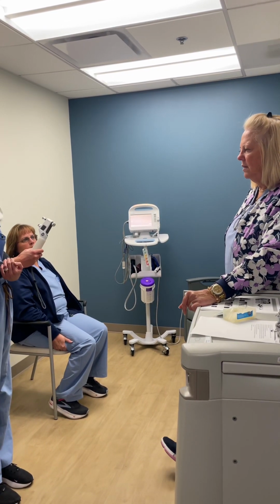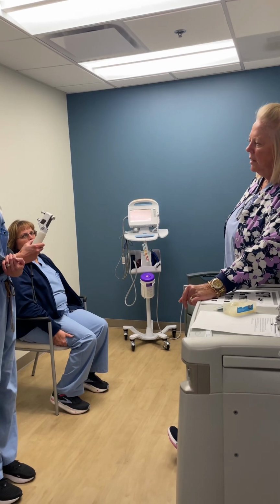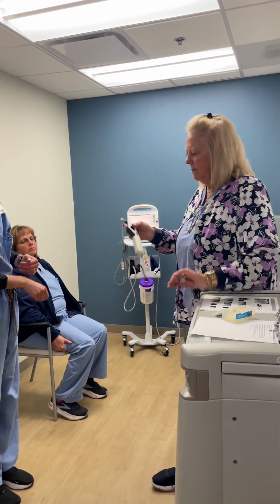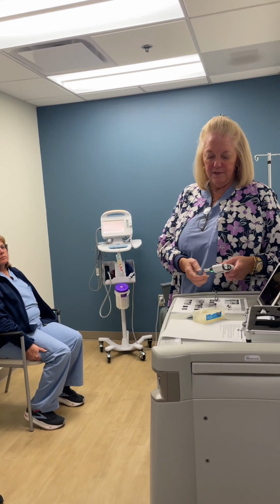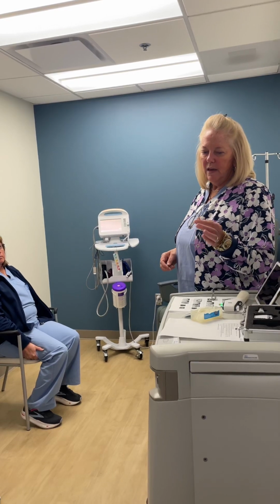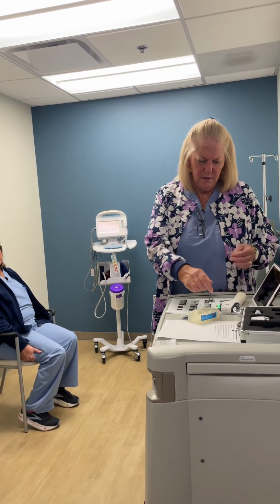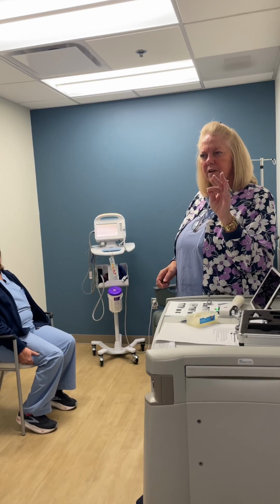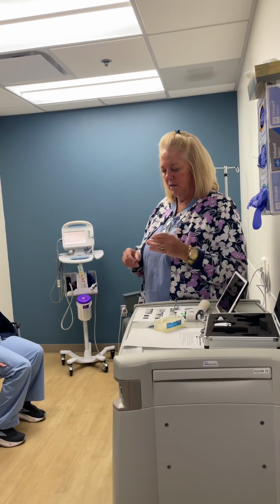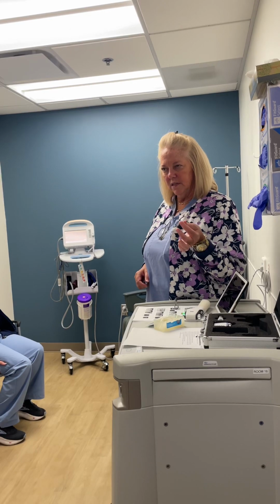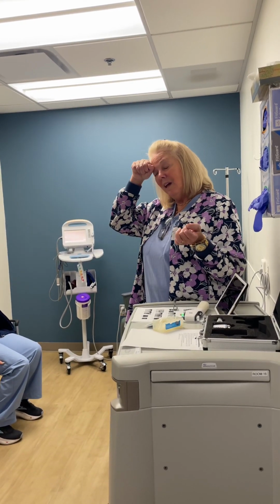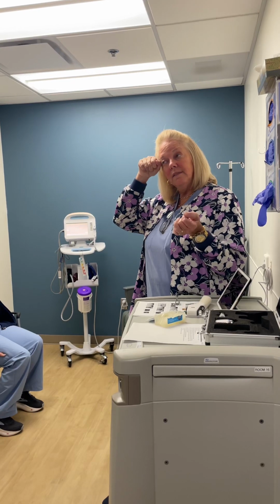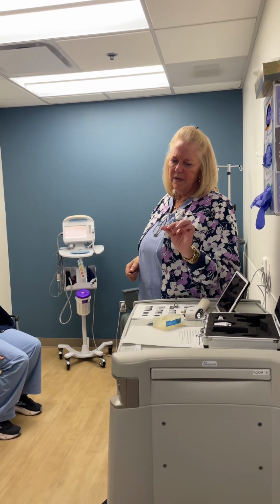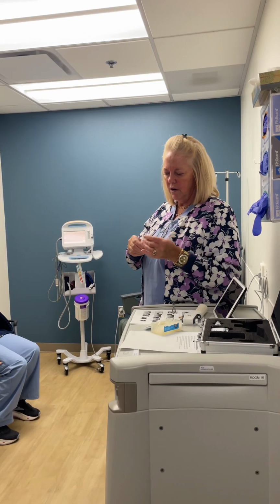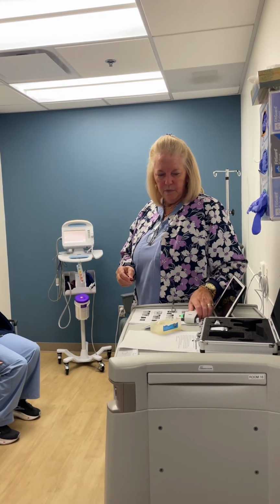What else can I say? Too high, too low. A lot of times with this model, you get static, and it's going to keep giving you an error message to repeat it. Take out the little piece here and rub it between your fingers, and that gets rid of the static. This piece also gets cleaned every 6 months. It gets soaked in alcohol. Actually, SPD will do it. They'll soak it in 70 to 100% alcohol and then rinse it, but it has to be dried really well, so they use the air dryer. And then just replace it and put it back in.